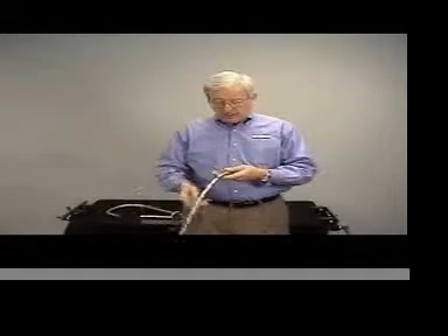All the arms you've seen so far are slightly different designs, but they're all opened and pre-tensioned in basically the same way. And here's how you do it. First, make sure that the arm needs to be pre-tensioned, as in this one. If you can hear the knuckles, it needs pre-tensioning. Check to make sure that the tensioning knob, the device we saw before that tightens the unit, is all the way loose, and that is turning it in a counterclockwise method until it reaches a stop.